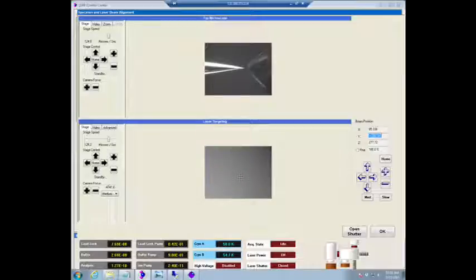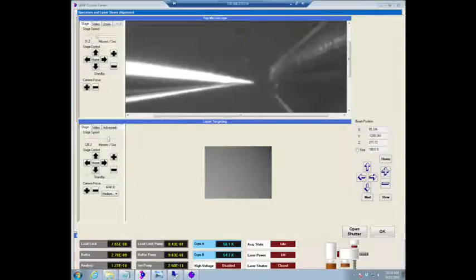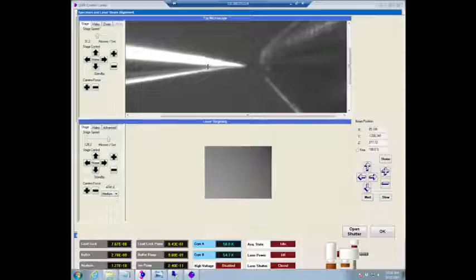And you move close to the local electrode. So if I zoom in here, you can see it's just right in front of the local electrode. You can also see that it's not a brand new local electrode, so it's already got a little bit of dirt on it. That doesn't actually interfere with the measurement at all. So don't change the electrode to a new one just because you see it in the camera and you already see a rough surface, which already gives you an idea that that's probably not going to work.